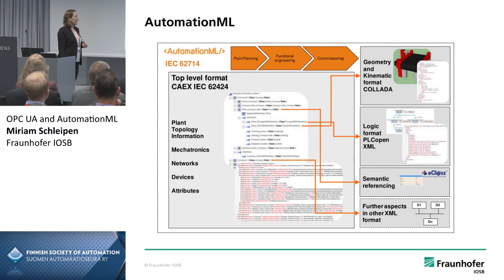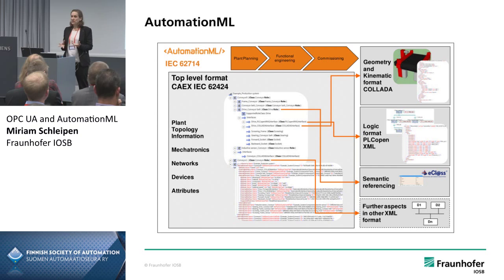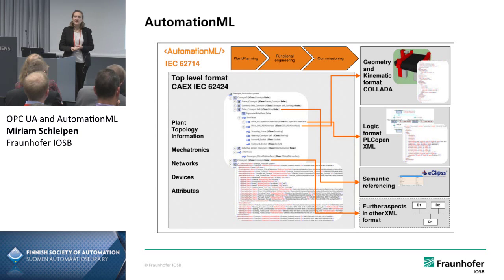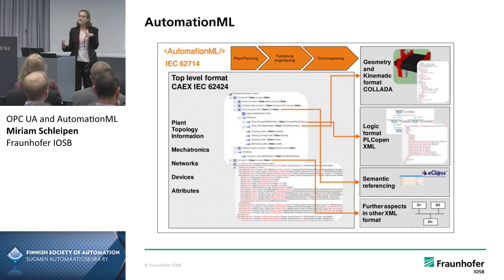With AutomationML you have a semantic description of your plant. You can describe plant topology information — for example, your communication networks, logical networks, physical networks, the attributes of your components, and also things like geometry information for an existing robot. AutomationML does not define any new XML format, but builds on different existing standardized XML formats and just defines rules for how to use and combine them. So the AutomationML IEC standard is not a long specification — only some pages to read.